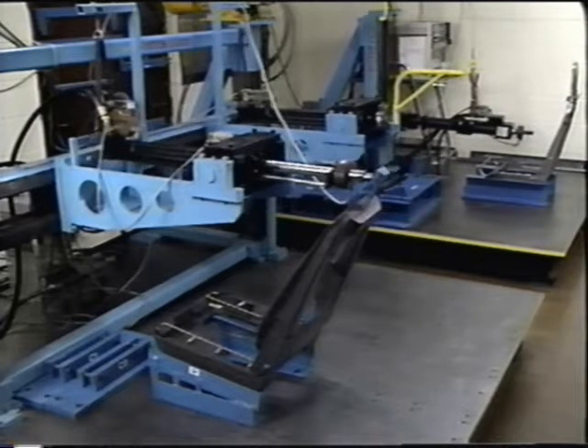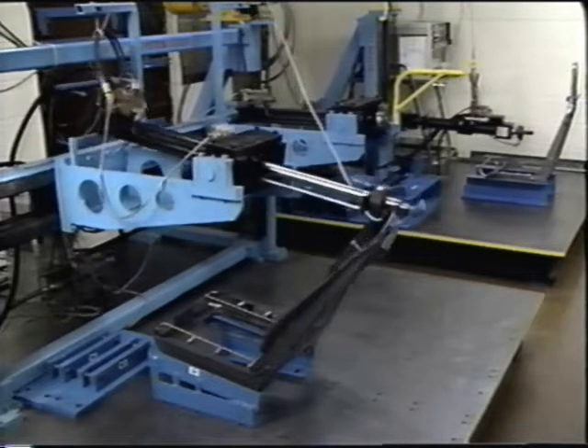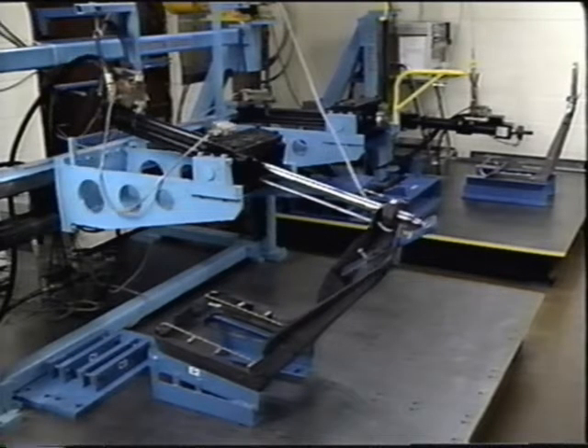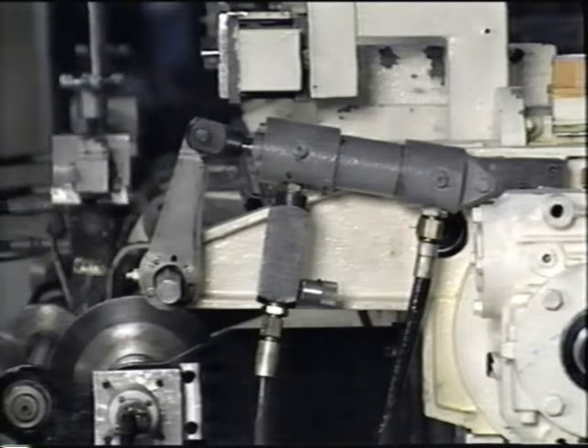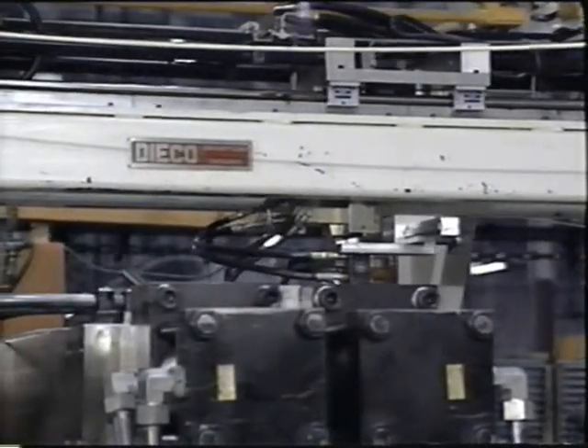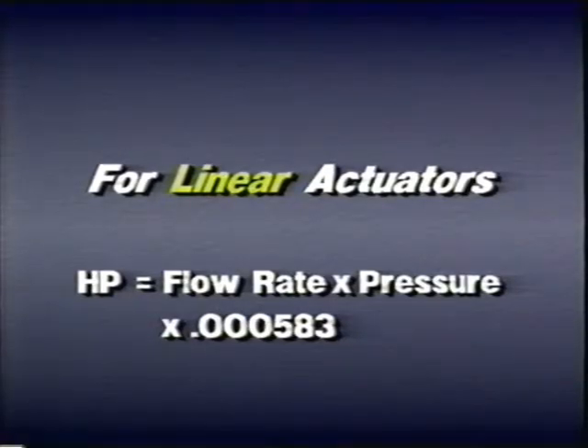Now, sometimes we don't know the speed or the force. For example, suppose all we know is the pressure and the flow rate. We can use a different, simplified approach that uses a special constant to establish the relationship of horsepower, pressure, and flow rate.